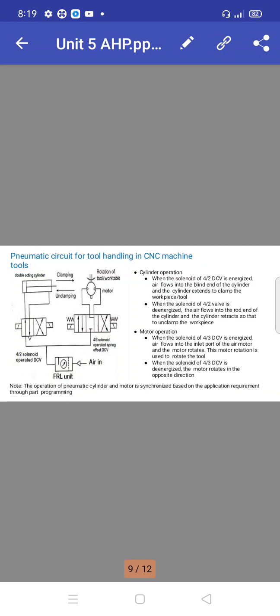When the solenoid of the 4/2 DCV is energized, air flows into the blind end of the cylinder and the cylinder extends to clamp the workpiece or tool. When the solenoid of the 4/2 valve is de-energized, air flows into the rod end of the cylinder and the cylinder retracts, unclamping the workpiece. This completes the cylinder operation.